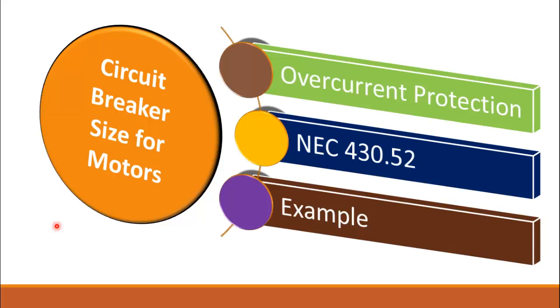In my previous video I explained how to size the circuit breaker for branch circuits that include lighting circuits or any resistive loads other than motor loads. For motor loads, we first need to identify the overcurrent protection. After that we will refer to the NEC standard 430.52, which states the circuit breaker protection for motors. Lastly, we'll solve an example to understand the sizing of circuit breakers for motor circuits.